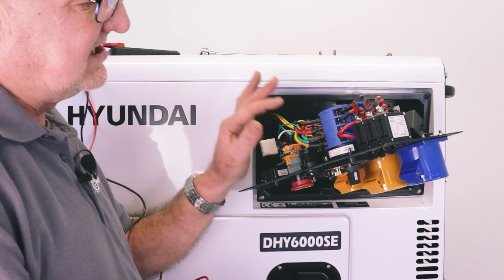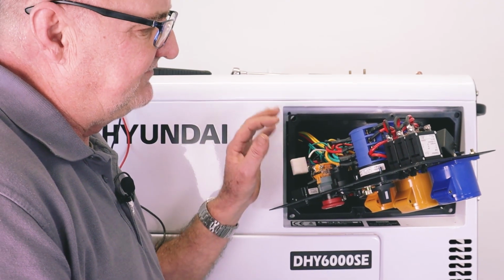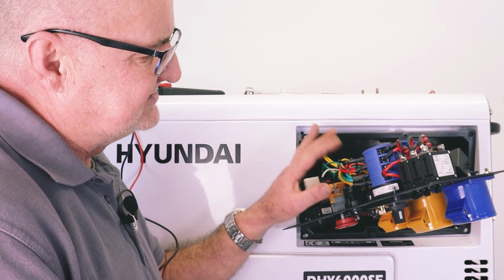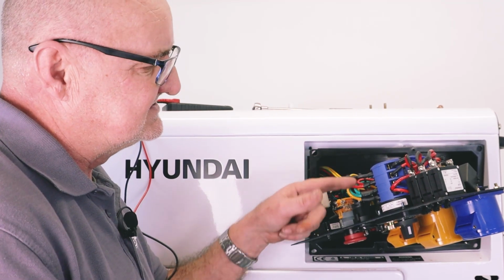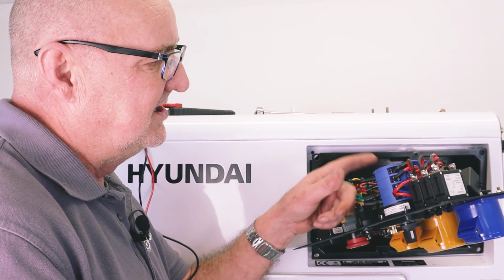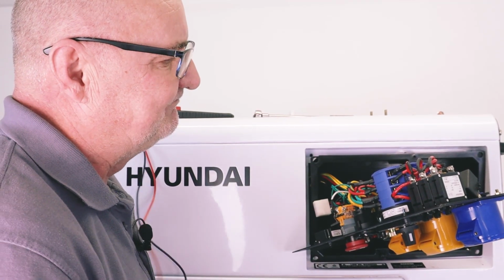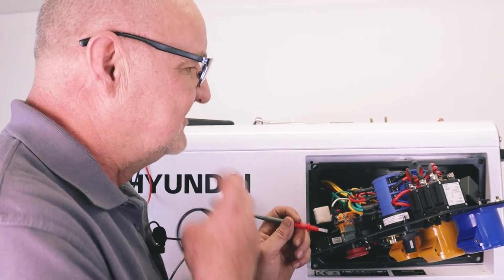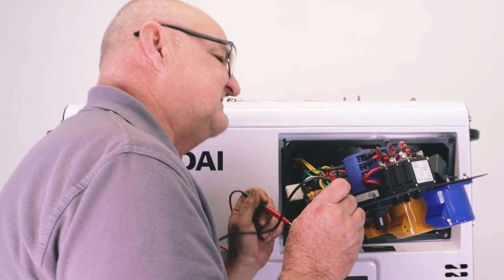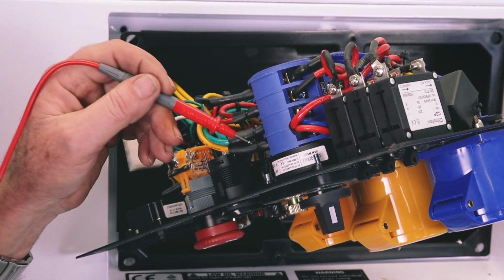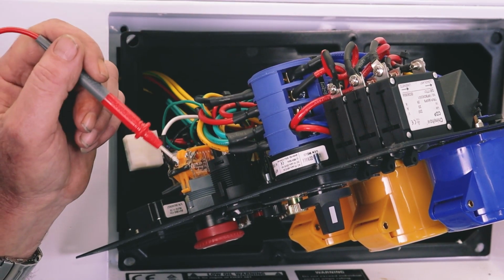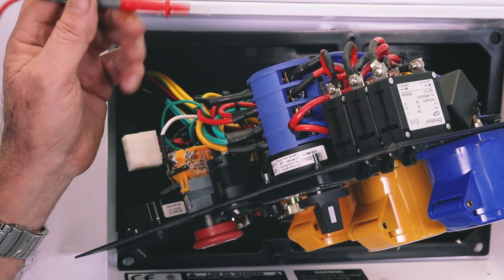If those voltages are correct, we then switch the generator off, and we know that our problem lies not in the generator side, because these are the main 4 wires coming in. We know it lies within the control panel. So again, what we could do is look at the negative. So let's say we had voltage here, we had voltage coming out, we could detect voltage coming out.